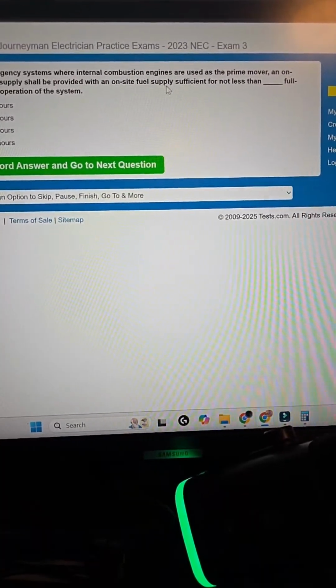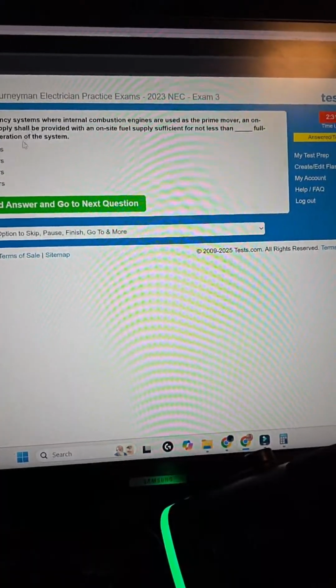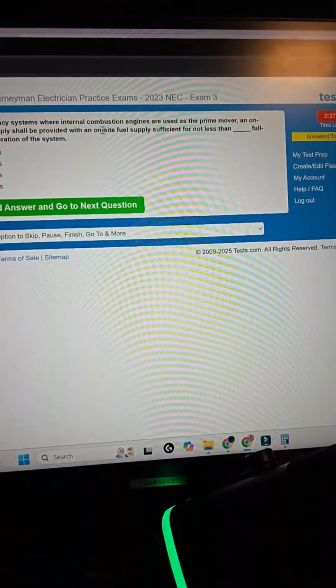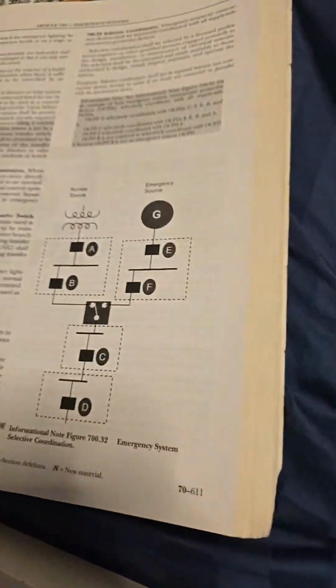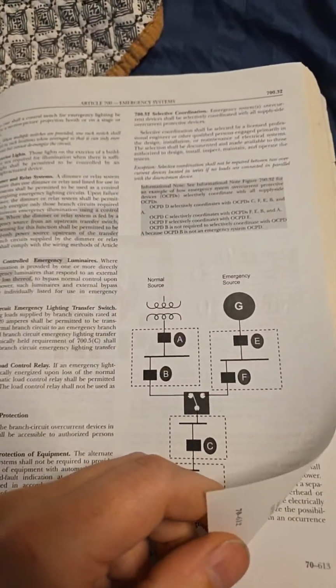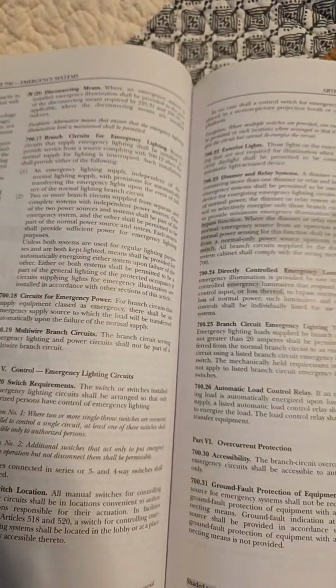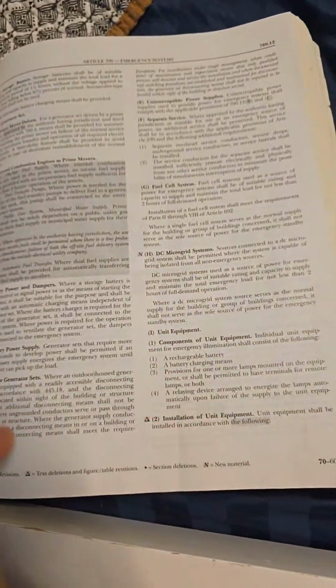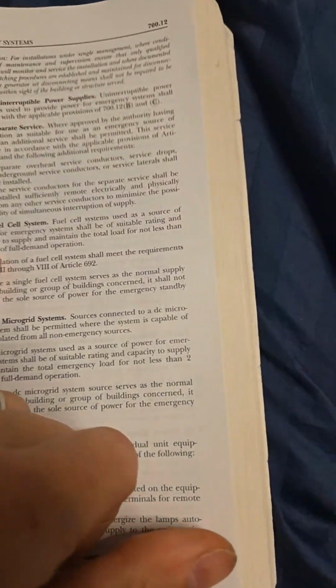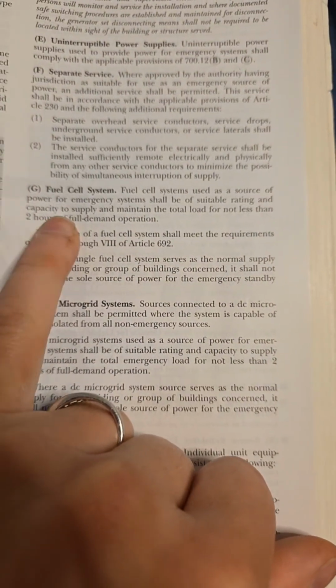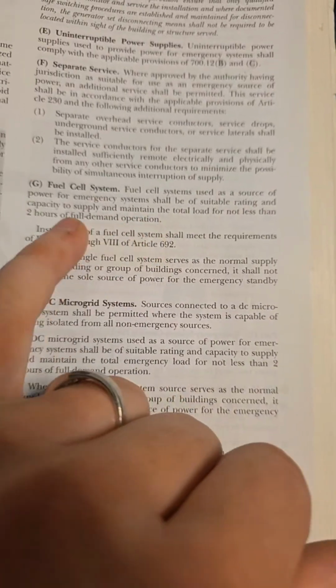For emergency systems where internal combustion engines are used as a prime mover, shall provide with an on-site fuel supply sufficient for not less than so many full demand hours. We could look this up if we wanted to. We'll look that up too. It'd be 700. So 700 is emergency systems, right here. And if we're looking for something about a prime mover, so let's see if we can find it here. It's going to have internal combustion. There's a generator there, components, fuel, right there, 2 hours, full demand, right there. I think for emergency systems, the source power, we're just going to go with 2 hours because we found it. Let's just do that.